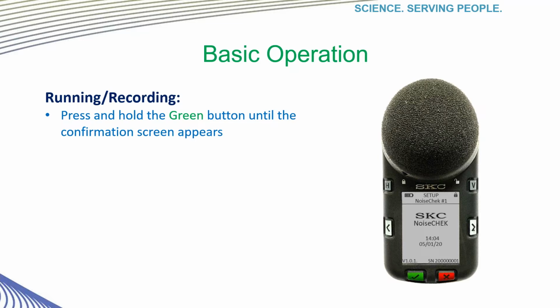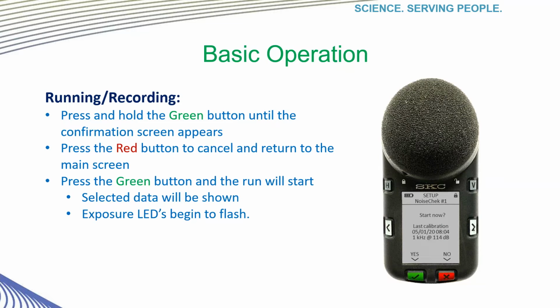Now that the calibration has been performed successfully, we're ready to begin our noise monitoring. To begin a run, just press and hold the green button until the confirmation screen appears. At this point, if you press the red button, you will cancel the run and return to the main screen. If you press the green button, the run will start. The selected data will now be shown, and you will now see the universal symbol for play or record shown in the upper right-hand corner, and that's the small triangle next to the padlock. And the LED at this point would now start flashing green.